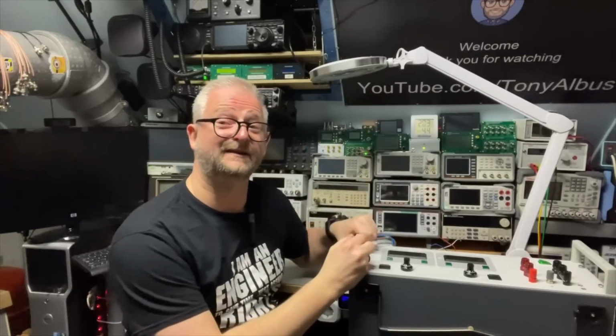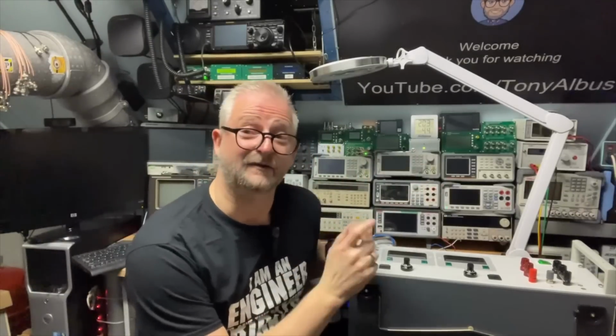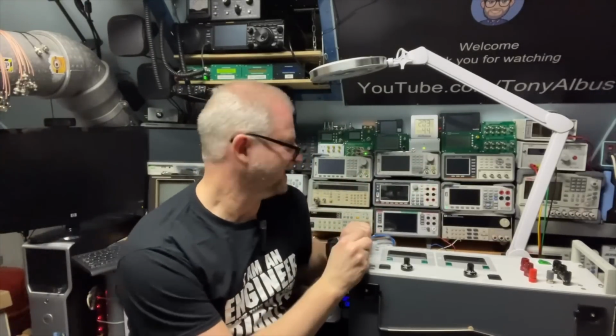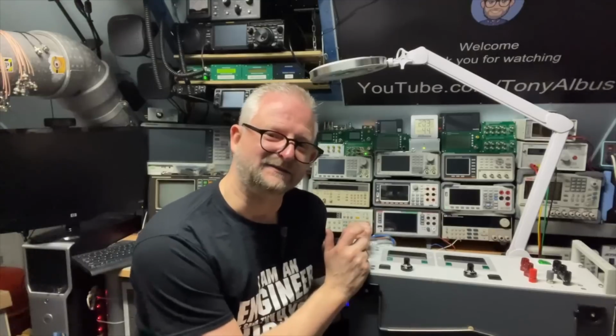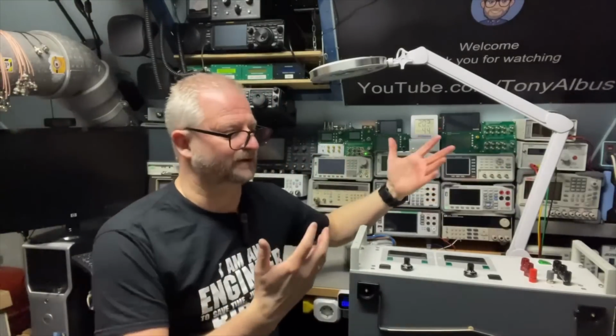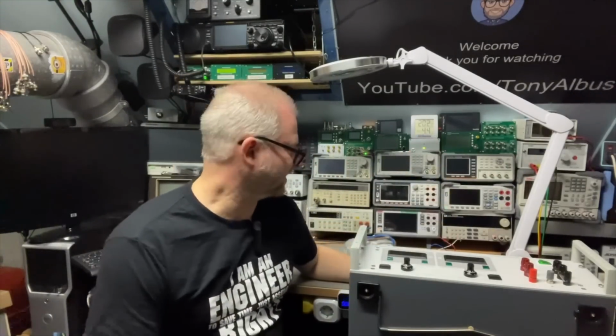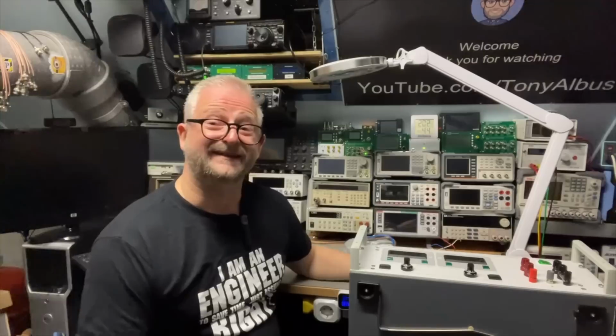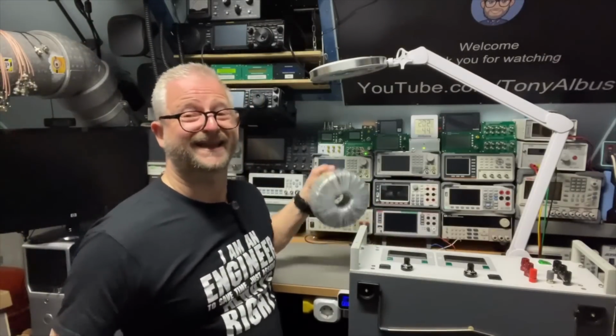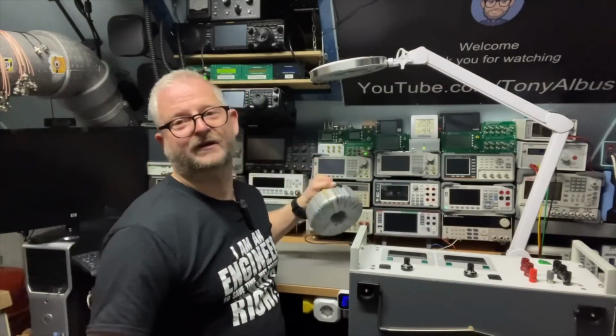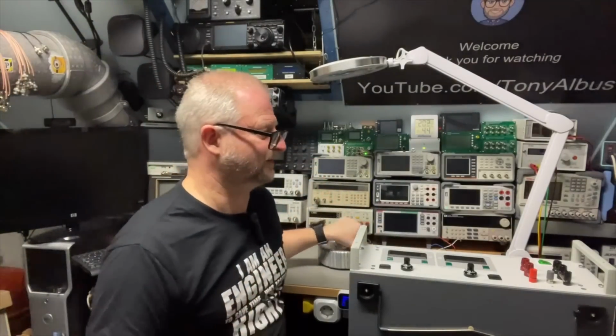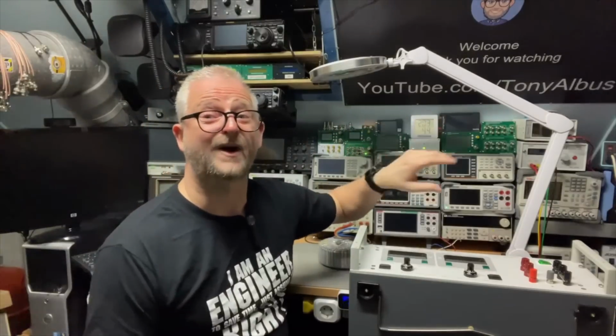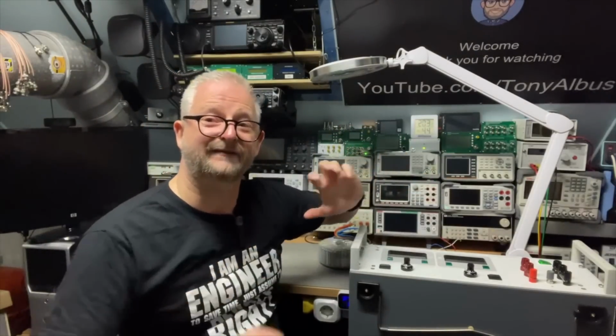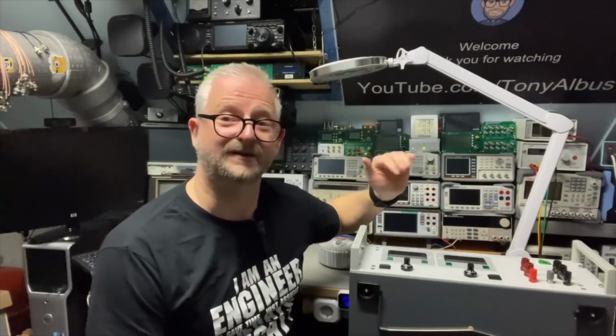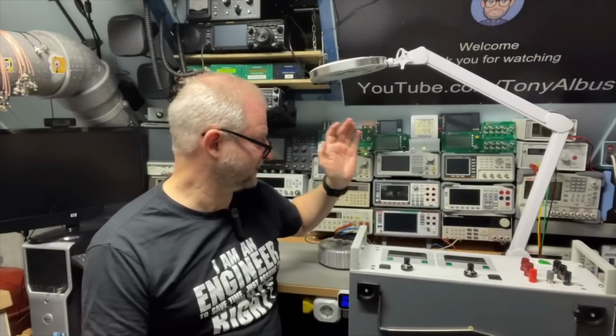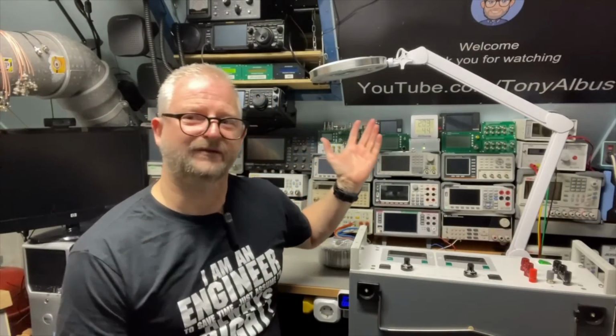Using the C-type fuses solved my problem, but it's not a really nice solution. It's good because it avoids tripping your fuses all the time. But this transformer still gets a current shock starting up, so it's not great for the transformer. Also the house wiring gets a real kick every time you have 100, 200 amps going through it for a short period, which I don't think is really good.